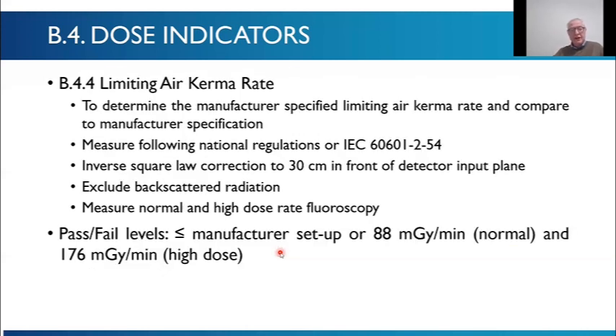Limiting air kerma rate: this is where you drive the system to its maximum air kerma rates and measure it, and then calculate with an inverse square correction the air kerma to what it would be 30 centimeters in front of the detector input plane, excluding backscattered radiation normally. There may also be some other local or national regulations that you should follow or may have to follow. That will depend locally. Then we have these pass-fail rates, for example, the 88 milligray per minute for normal mode and 176 milligray per minute for the high dose, a factor of 2 higher. Or there could be some manufacturer setup that you've requested that limits this to lower than that.